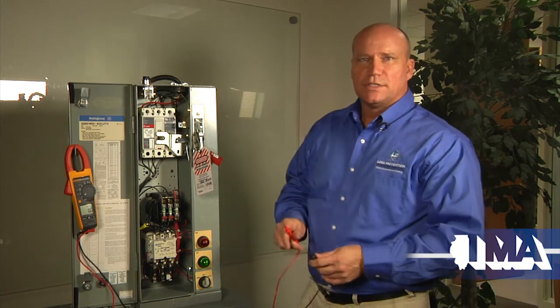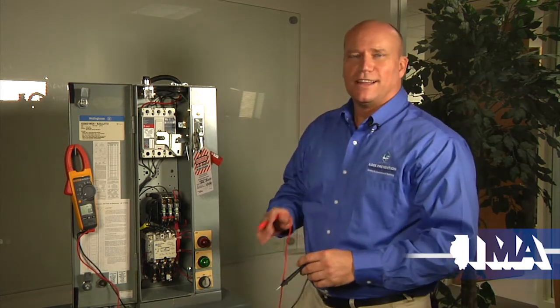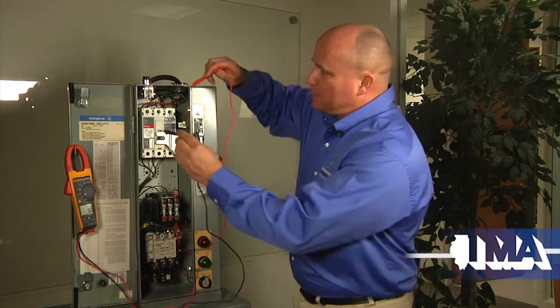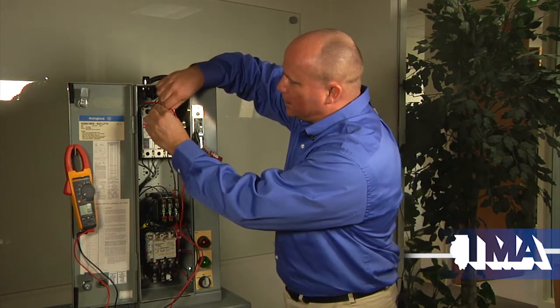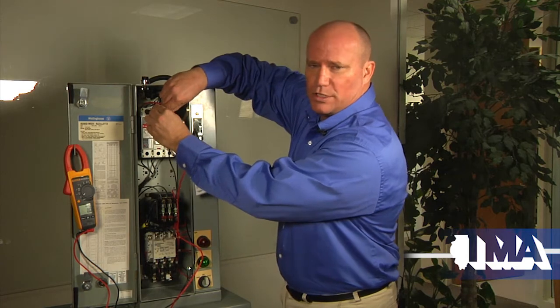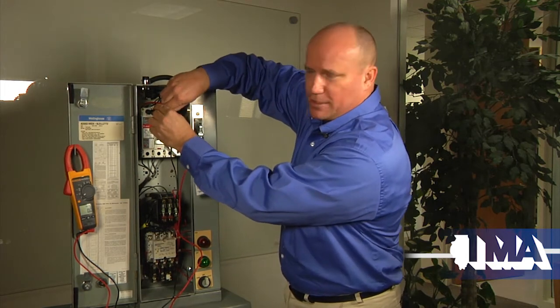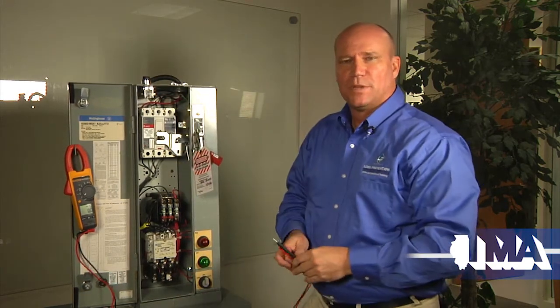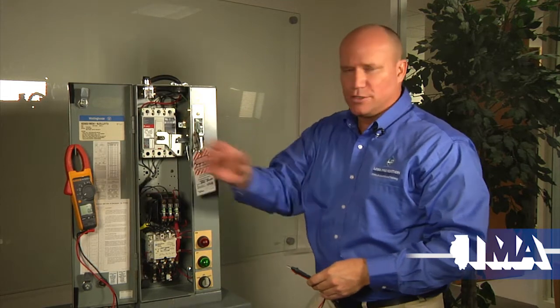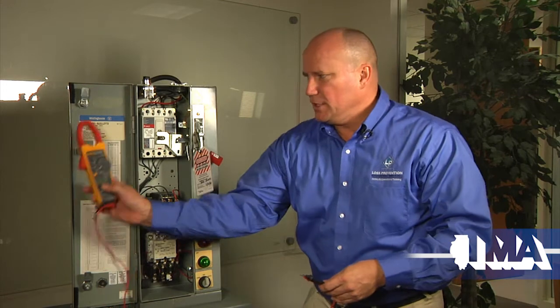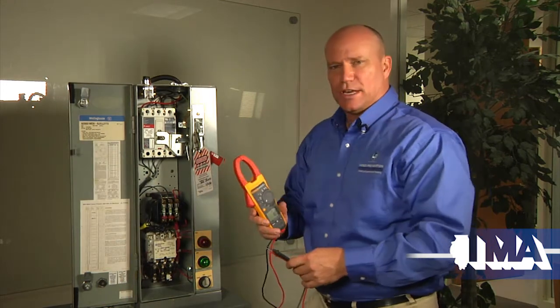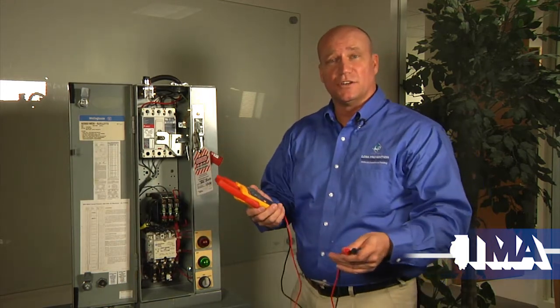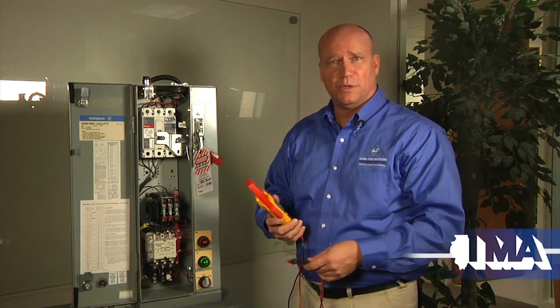Now, if you don't have voltage, and the reason I left this open is, the last thing you want to do, and this is really, really important, is why they call it live, dead, live: I want to verify again on a known live source. That can be just one check, to verify that the meter deflects as you would expect. If this was energized, I would get 208 volts on my meter. Why is that important? If I use my meter to check it de-energized, and in the process of doing so it failed internally, every subsequent reading would be wrong.